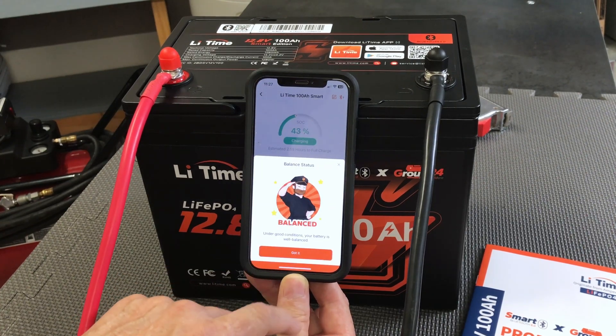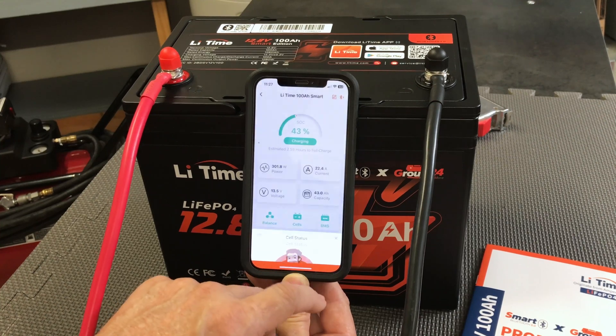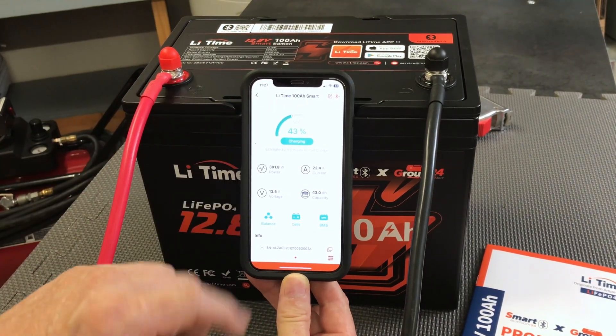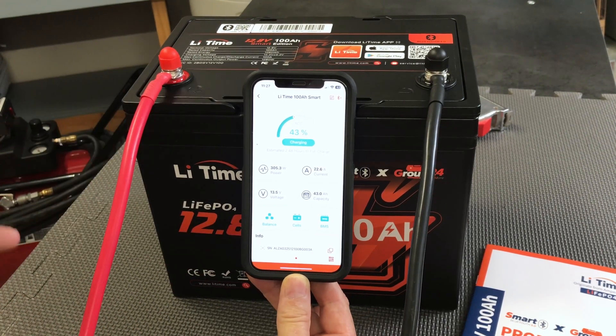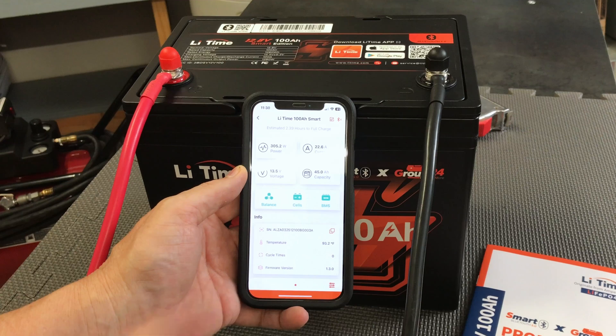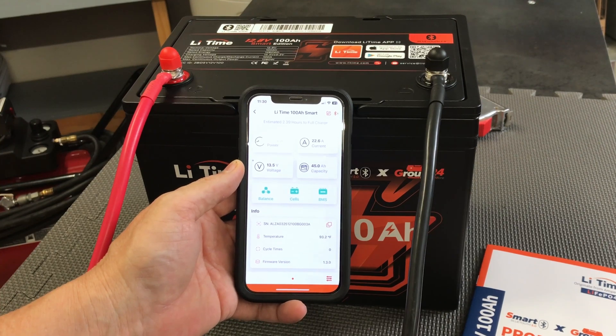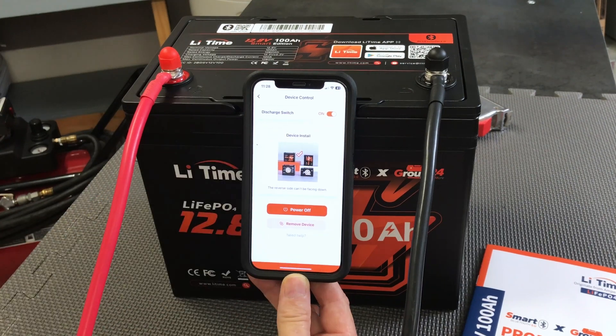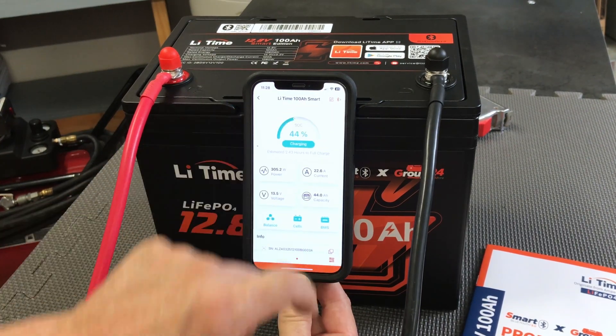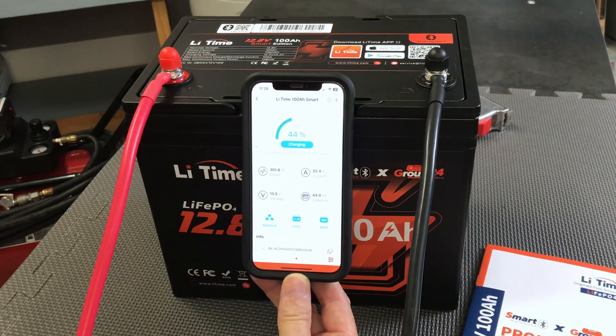You've got three items you can click on — it shows balance: yes, it's balanced. It doesn't give individual cell readings, but it tells you the battery function is normal and the BMS is normal. You can program in whatever name you want, and give it a badge or icon if you have multiple batteries. It also shows battery temperature — currently 93.2°F on the BMS and battery cell temp. You can toggle discharge on or off, essentially shutting the battery down.